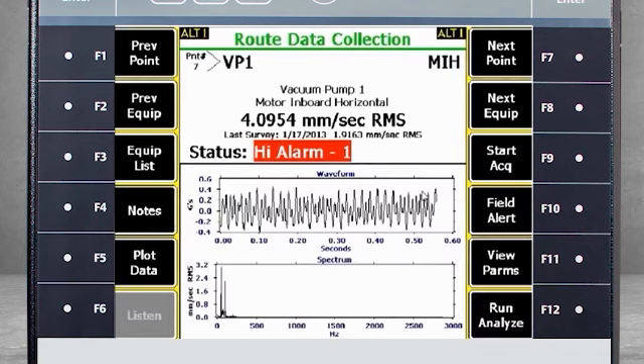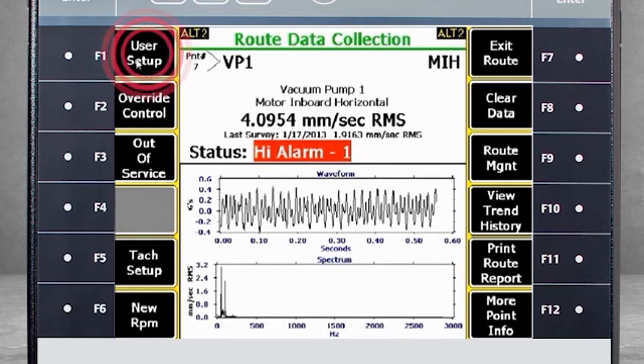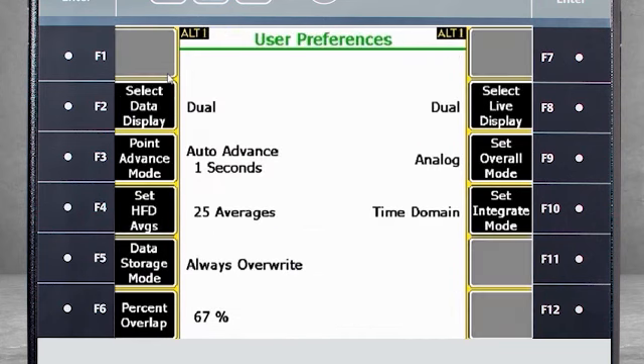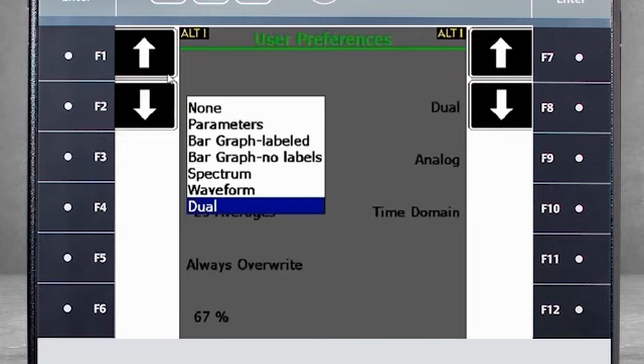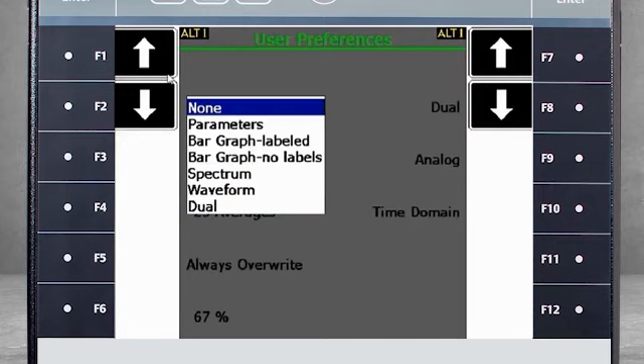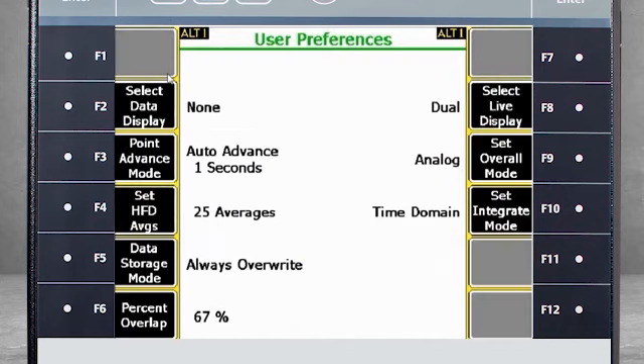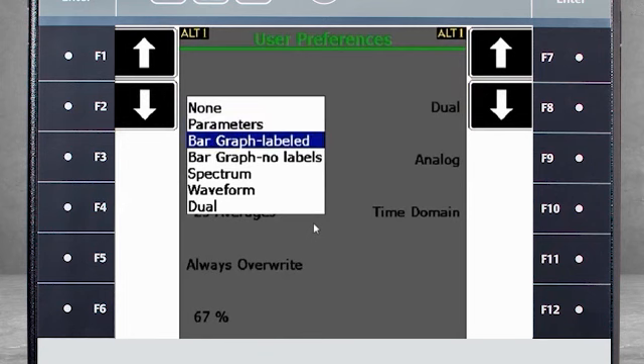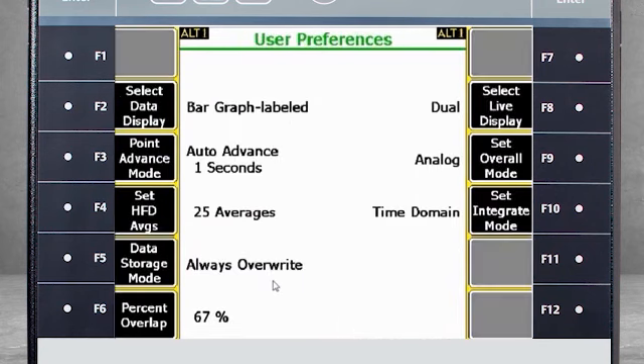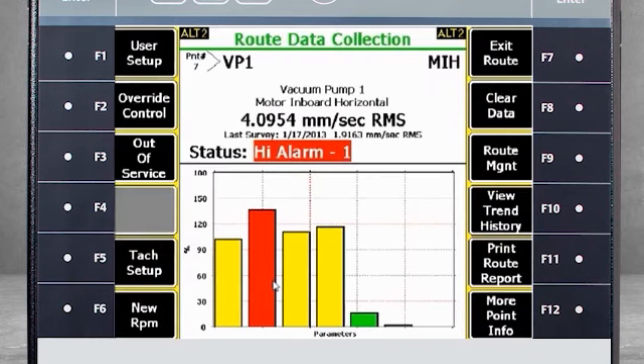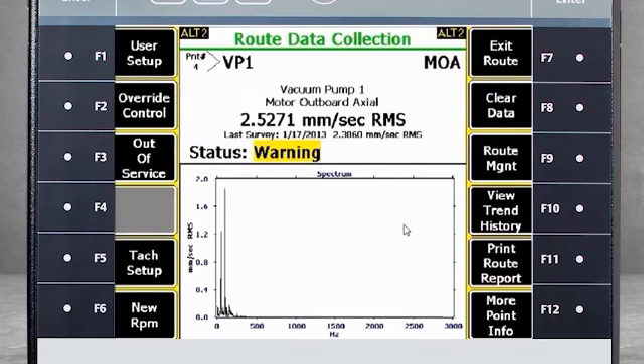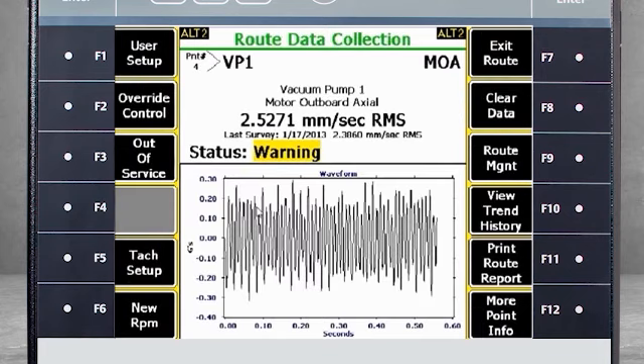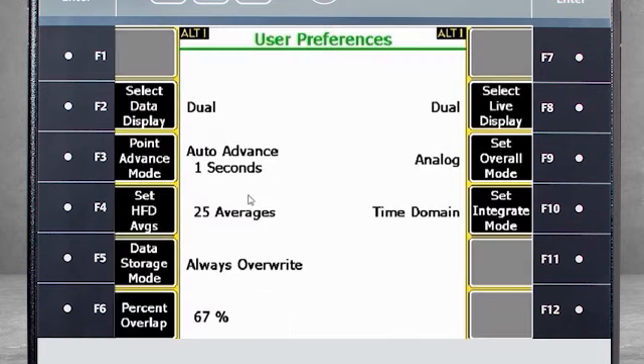Now let's move to the function keys on the Alt-2 screen. F1 User Setup is where you configure what you want to see on the analyzer screen, both during and after data collection. F2 allows you to determine what data will be displayed in the bottom half of the screen following collection on a measurement point. If I select None from the menu, nothing is displayed. If I select Parameters, I see a list of the narrow bands and their alarms. I can select Bar Graphs labeled or Bar Graphs without labels, Spectrum, Waveform, or Dual to display both the spectrum and waveform.